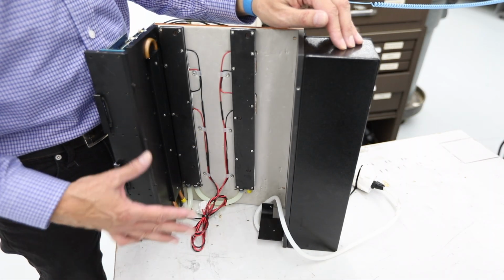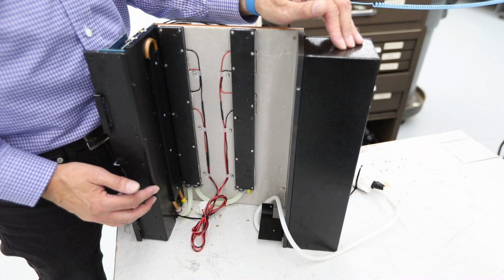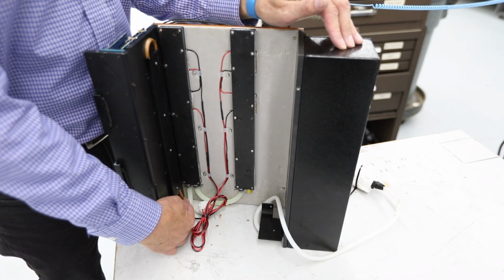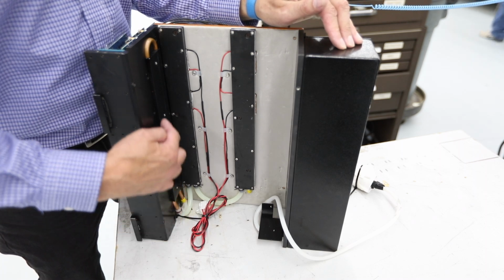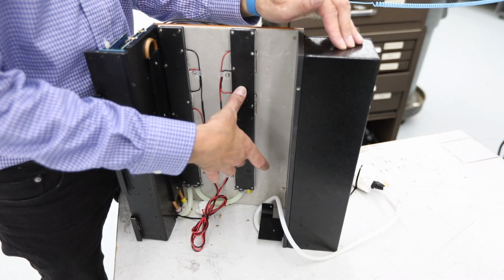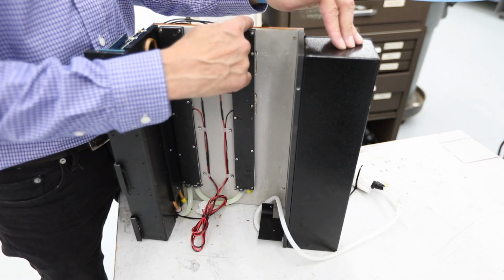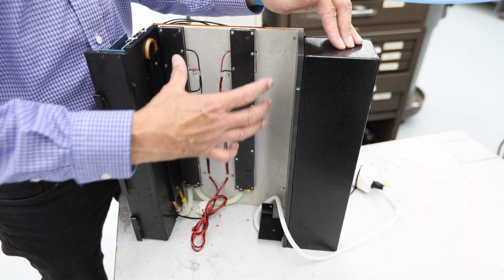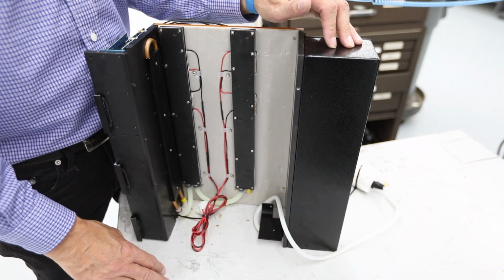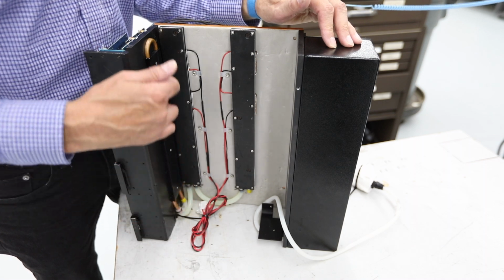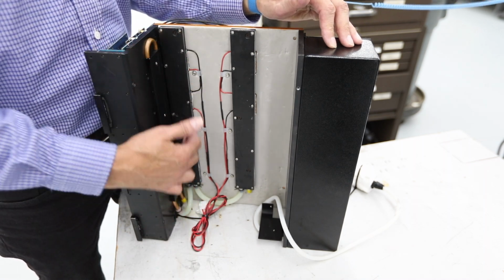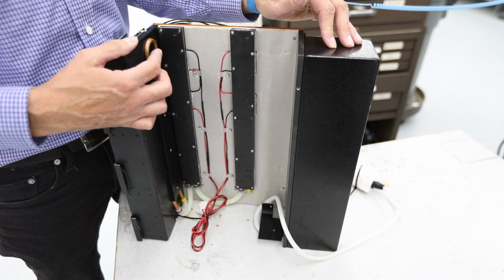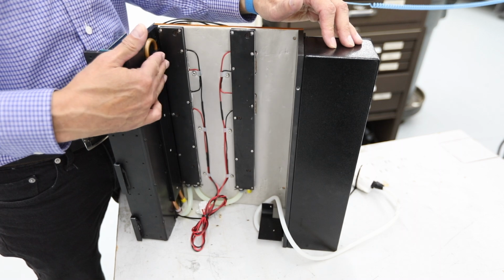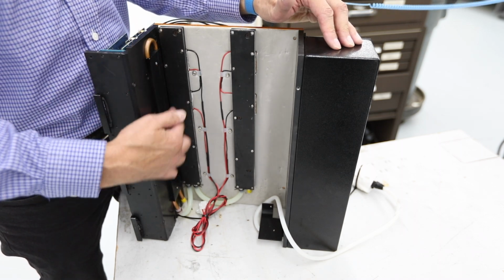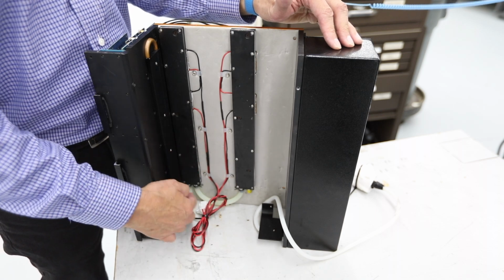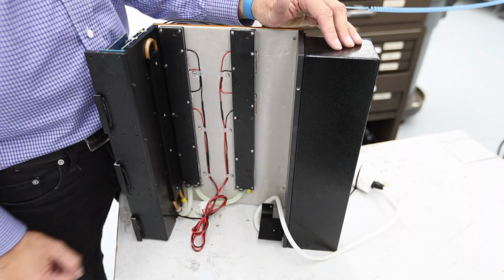So here we have the lower side of the optics imaging head off of a thermal system, showing you where the liquid cooling comes in here. So the liquid cooling is going through, in this case, 3 cooling chambers. We have 2 mounted underneath the laser diode head. This is cooling the heat away from the diodes, back down through the radiator and back to the liquid coolant tank. And on a thermal system we have a 3rd cooling system here, cooling the laser driver boards. On a UV system, because they use much less power, we don't need to liquid cool the laser driver boards. So again, it's a closed loop system, fixed cooling chambers with our 2 pipes going back to the lower coolant tank.